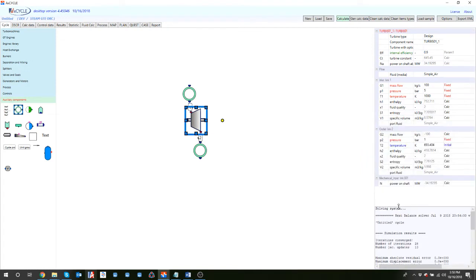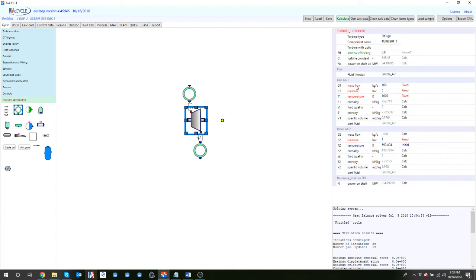Looking at what we just did: we specified fixed values for mass flow, inlet pressure, inlet temperature, and outlet pressure. The outlet temperature I had specified - either 600 or 800 - was not a physical solution the software could converge to. Therefore, it changed to the value that makes sense based on the turbine efficiency. If I decrease the efficiency, there is less enthalpy drop, and the outlet temperature will be higher, which is exactly what we see.